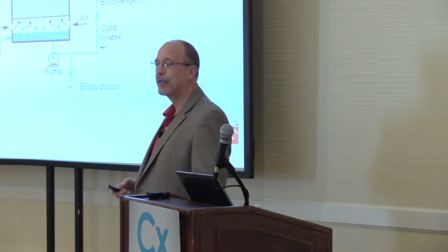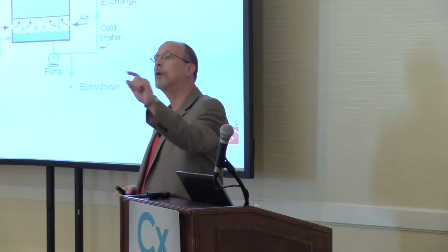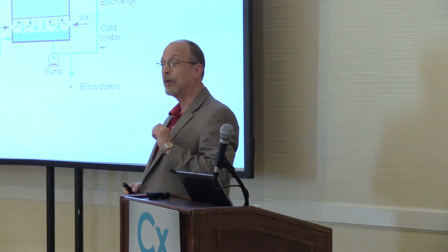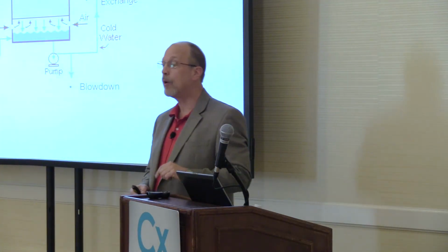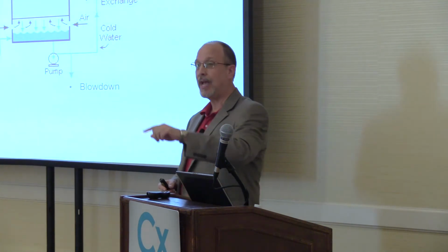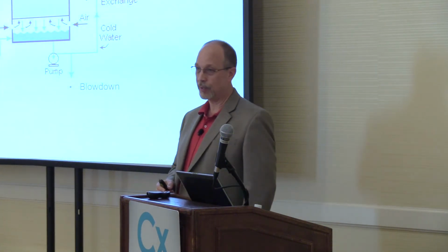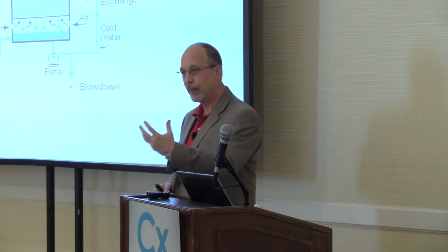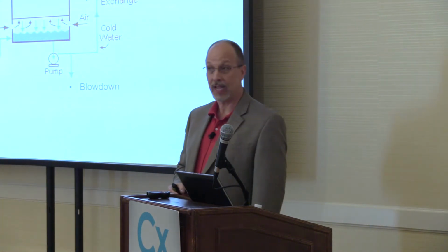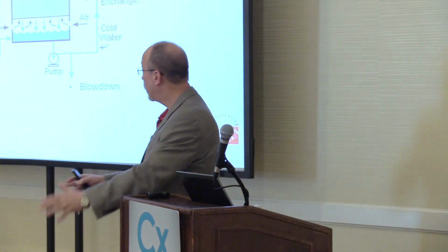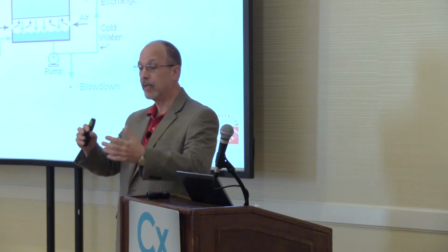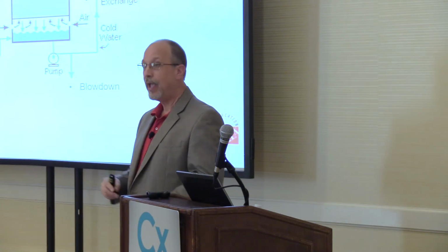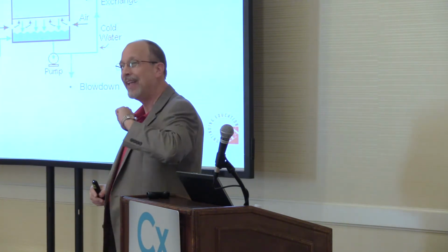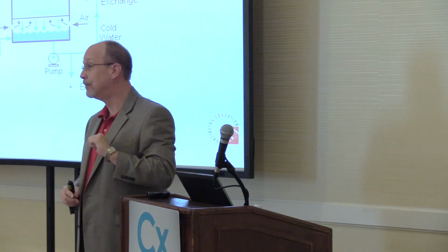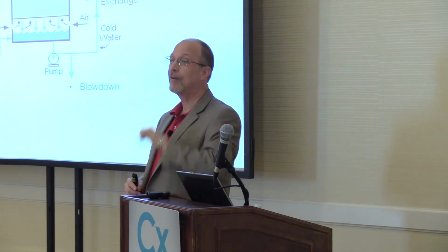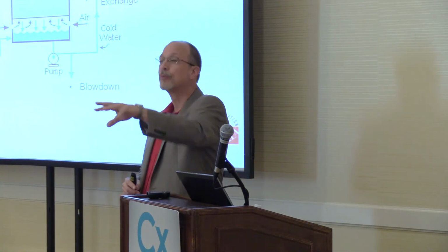All of a sudden, somebody wants to measure it because it's going to the sewer. So either you, the facility, wants to measure it, or in a lot of cases, the municipality says how much you're sending to the sewer. And this can be a simple or a very difficult application, because when the blowdown comes down, it's usually in an oversized line, and it comes blurp, and the pipe's usually not full. Very difficult application to measure blurps.